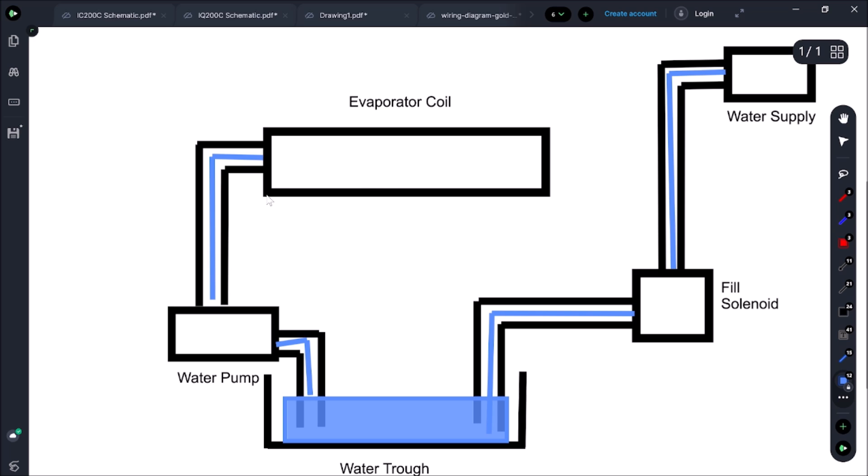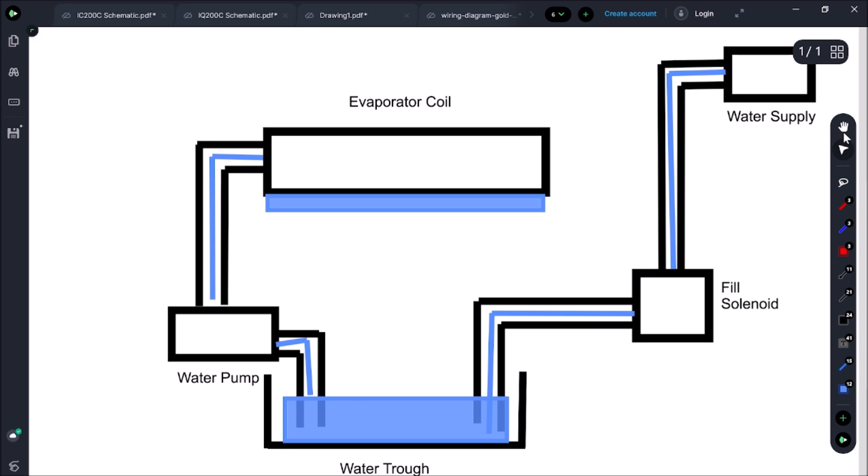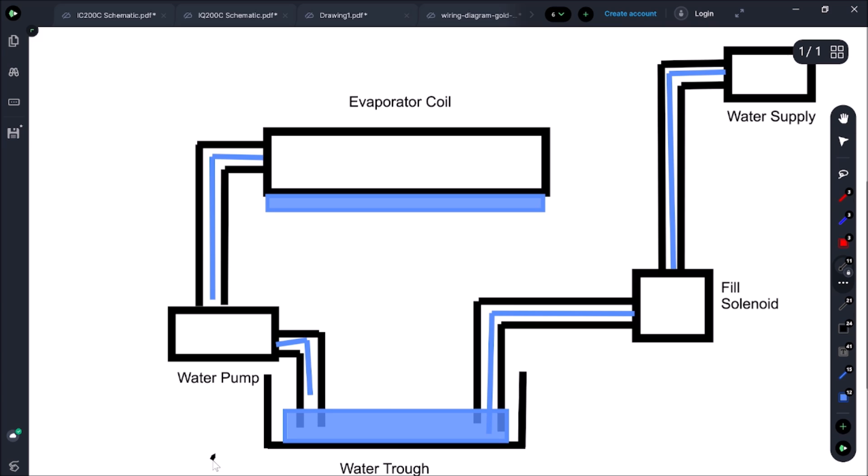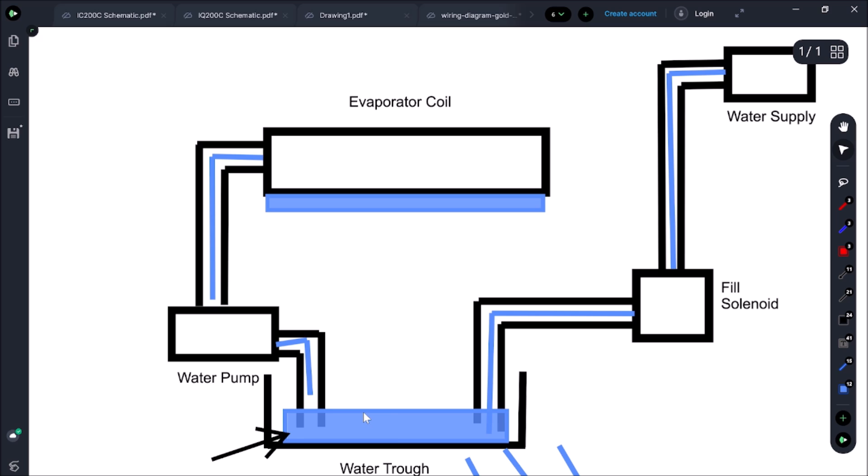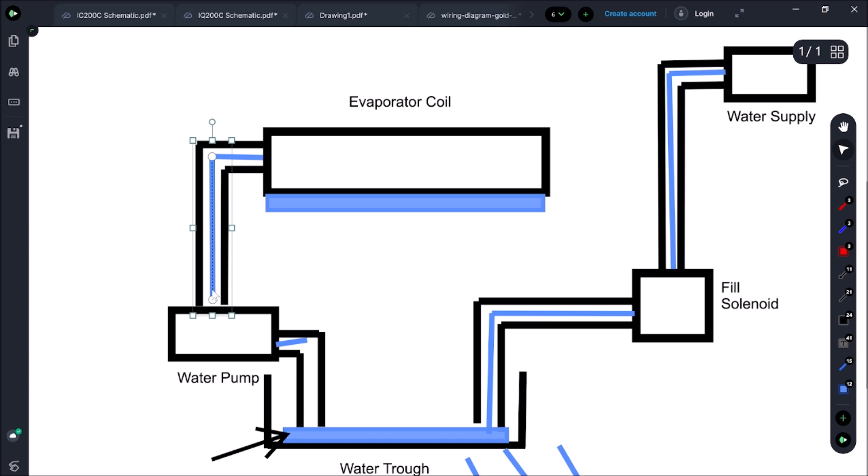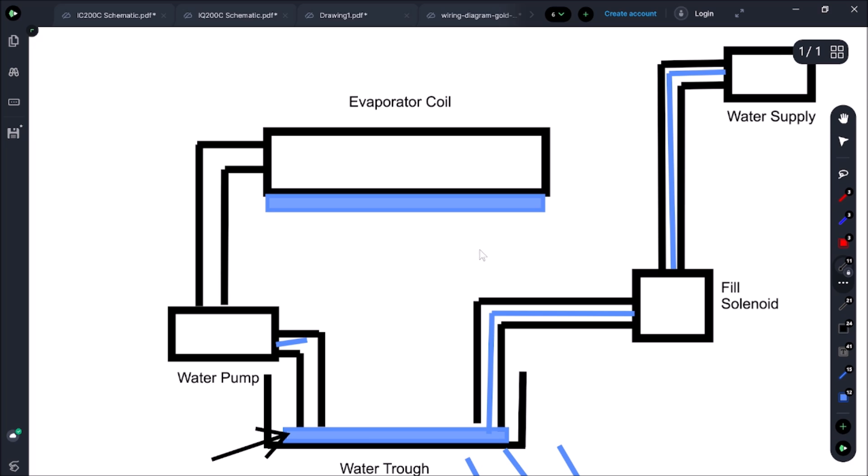What's happening here is we have a little bit of ice on here. As we know if we get ice on there this starts dropping this level. We drop below this level right here, the pump can't pick it up. So what's happening is the water is actually leaking out of here, leaking into the bin. If that leaks this is gonna drop down and we're below our pickup point on the pump right here. If we're below that point obviously we're not getting any suction, no discharge from the pump, and it means our coil is no longer going to make a thicker slab of ice. So we're losing water through here through the trough. Let's go investigate why that's happening.